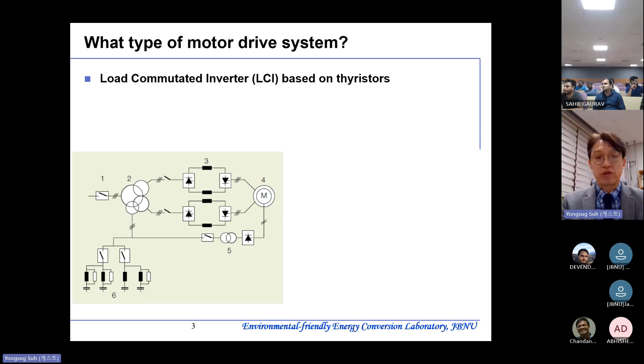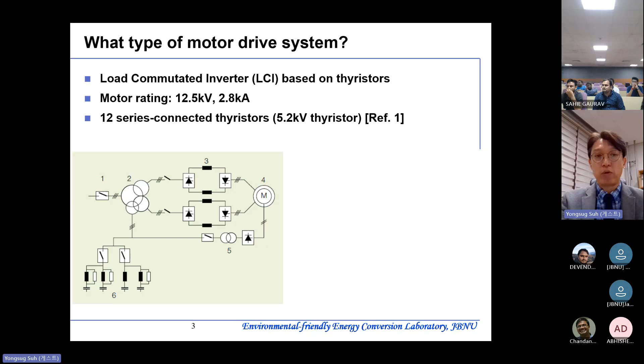The motor rating is around 12.5 kilovolts, 2.8 kiloamperes, and as you can see from this schematic, there are 12 series connected thyristors. You can see this single thyristor, but it's not a single device. You connect 5.2 kilovolt thyristors, as many as 12, to support 12.5 kV. So in medium voltage drive systems, series connecting power electronics devices is very common, and this is an actual photo of those 12 series connected thyristors. You can see here there are 6 so-called valves, and each valve consists of 12 series connected thyristors.